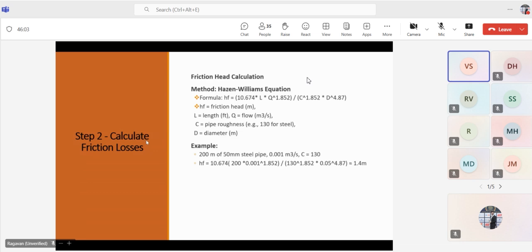So the first one, because our calculation is going to be based on the Hazen-Williams equation. Most people are already aware of this one. The hf, which means the friction head, is equal to 10.674 times L times Q to the power 1.852, divided by C to the power 1.852 times D to the power 4.87. This is the SI unit. In the imperial unit you have 4.7. All other things are similar. Only the constant value will be changed.